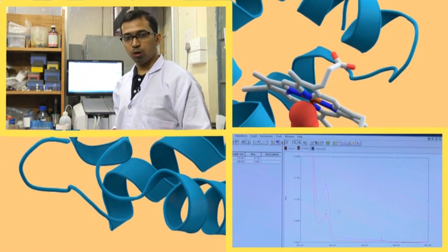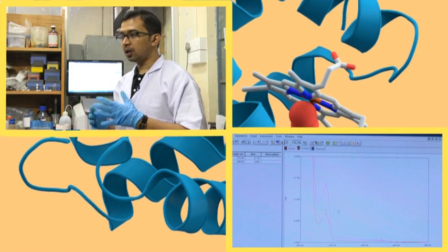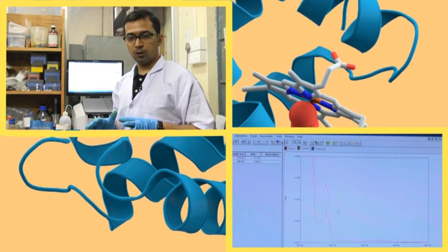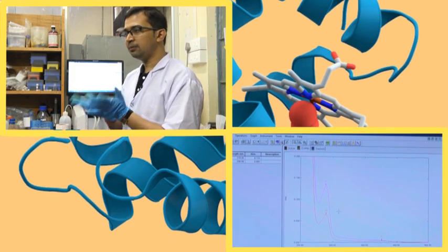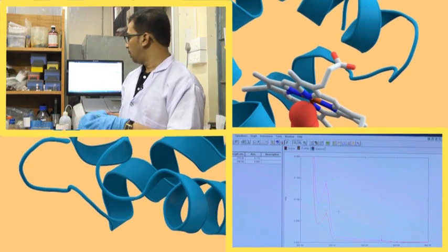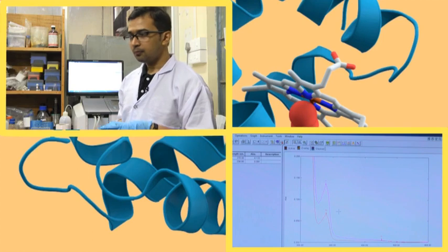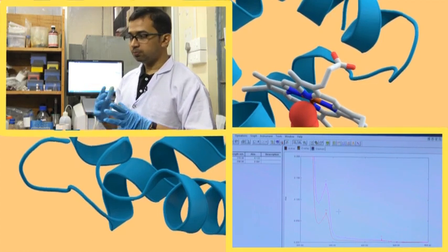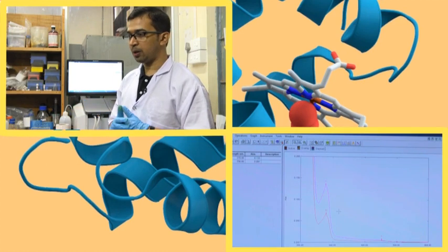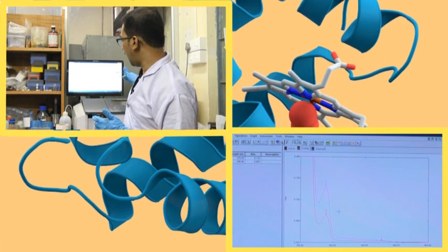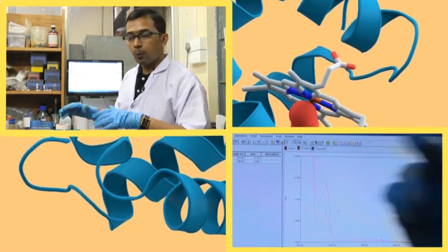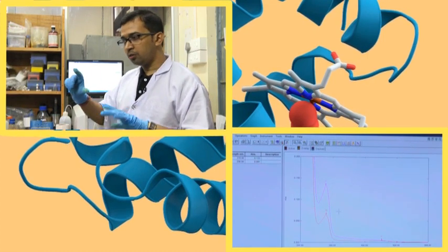You can keep it as slow also, and for slow scan speed the absorbance value is much more accurate, whereas for fast scan speed the absorbance value is sometimes accurate, sometimes may not be accurate, but out here we are keeping it at medium. Now, there might be some correlation with the change in the rate of this absorbance measurement, because while the absorbance measurement is going on from 600 to 200 nanometer, within that time the solution is kept still.